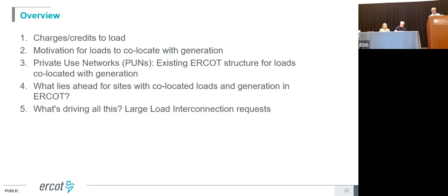So once you're energized, let's talk energy settlements. If you have generation behind the meter—you might have multiple meters, but behind those meters you have generation and load—it doesn't matter what type of generation it is, whether existing or backup. In ERCOT, energy settlements are recorded on a 15-minute settlement interval, and it's the net as measured at the point of interconnection. So if the load consumes 10 megawatt hours in a 15-minute interval, and the generation produced 6 megawatt hours in that interval, the load is charged for 4 megawatt hours. It doesn't matter when it occurred within those 15 minutes—it's just the net on that 15-minute basis. So if it's net consumption, it's a charge.